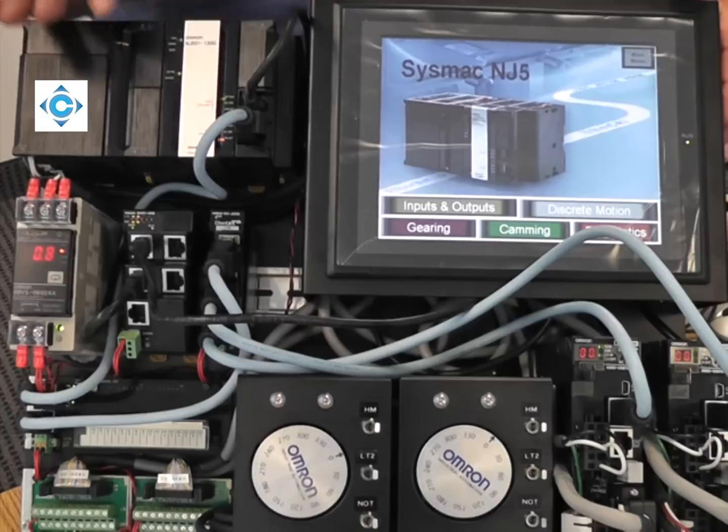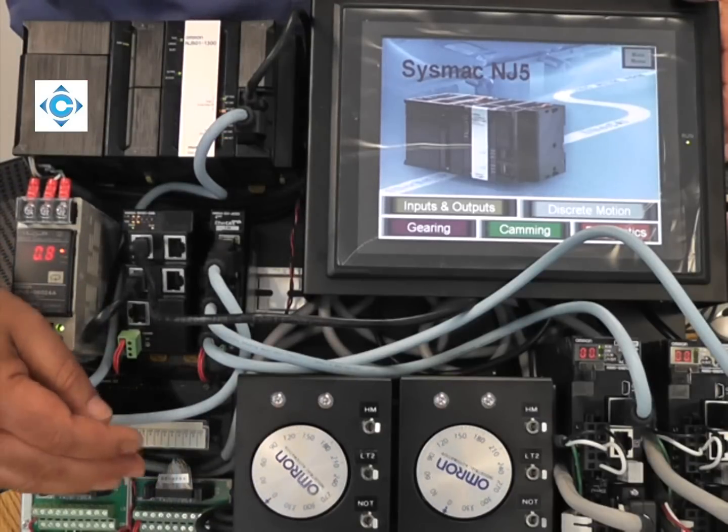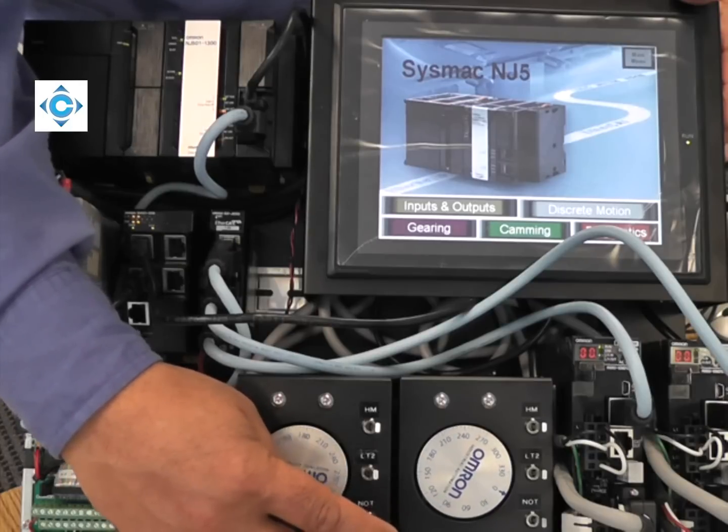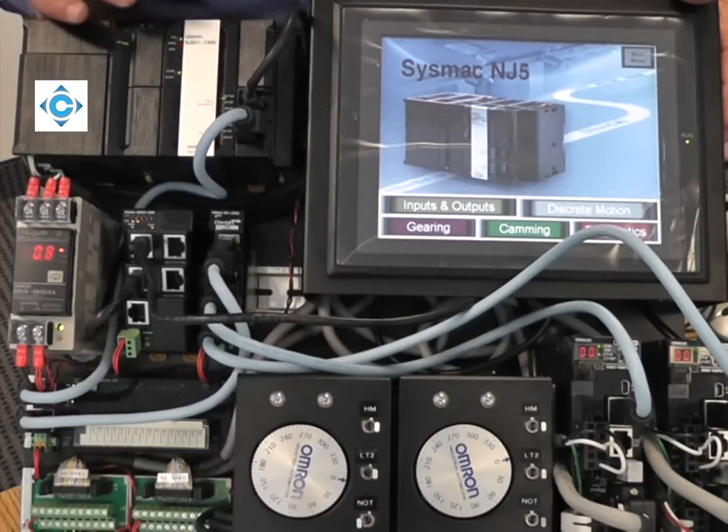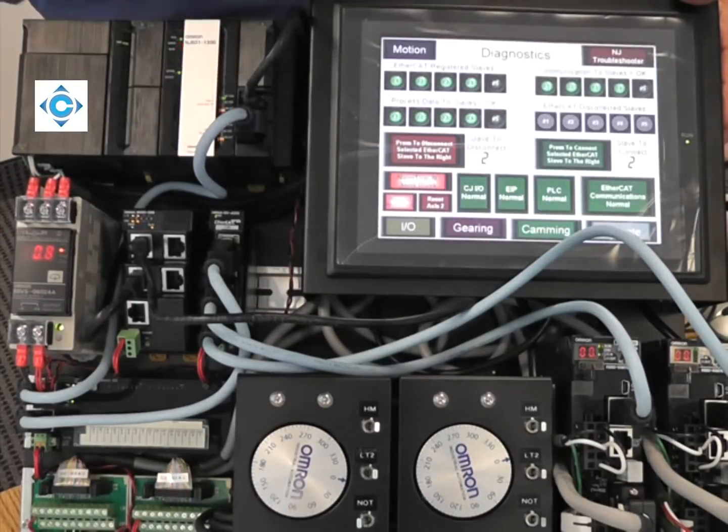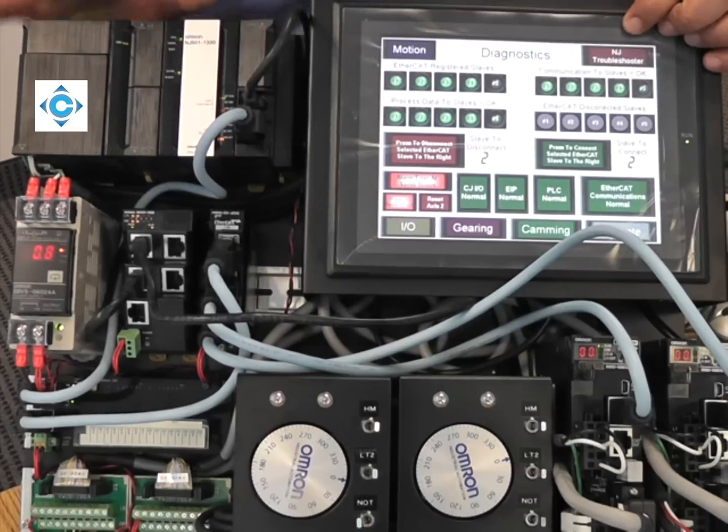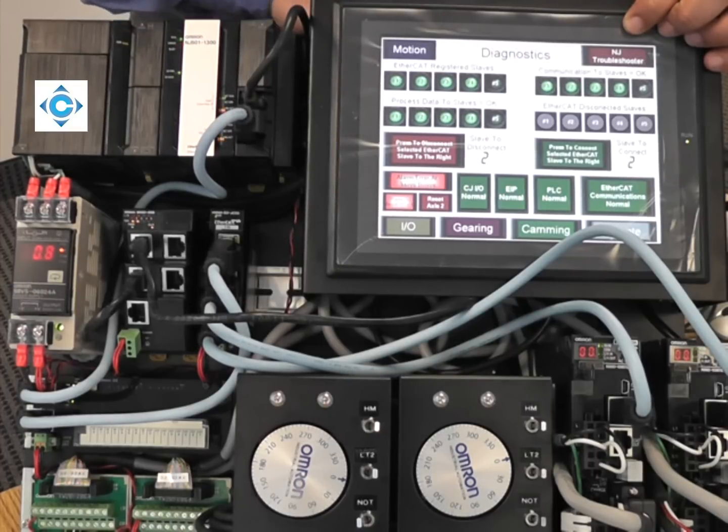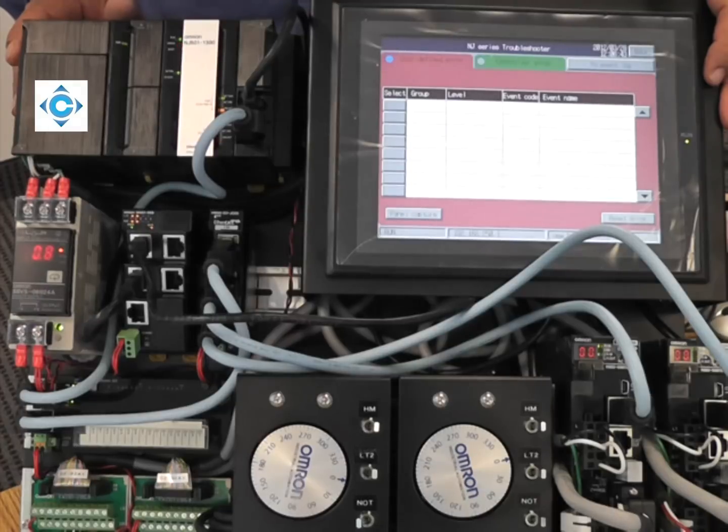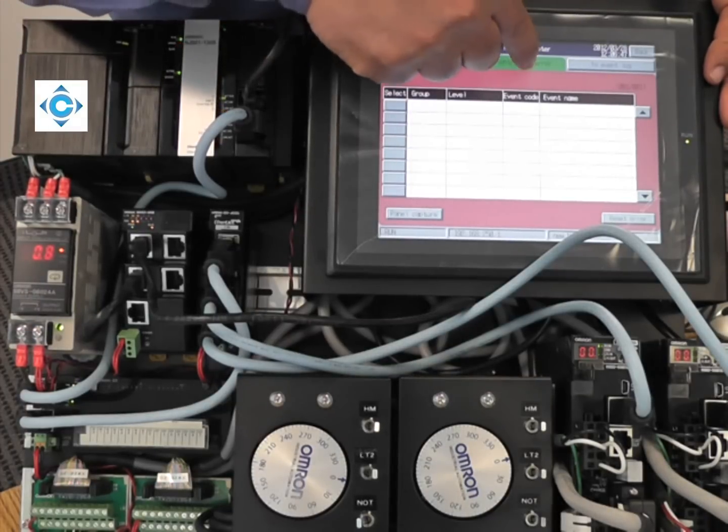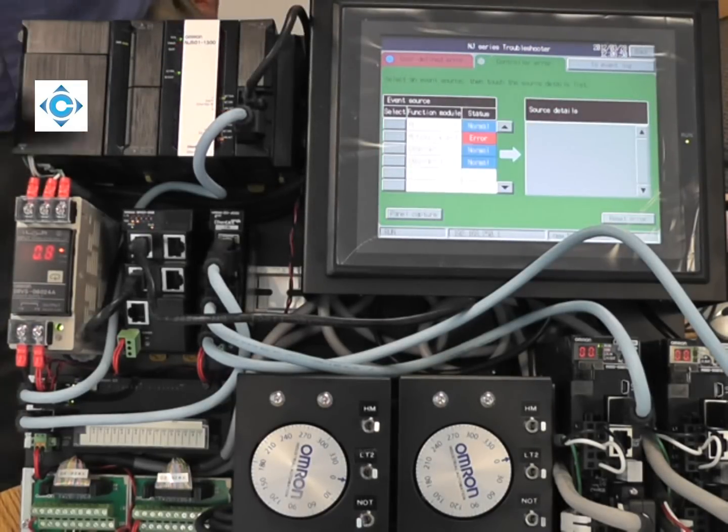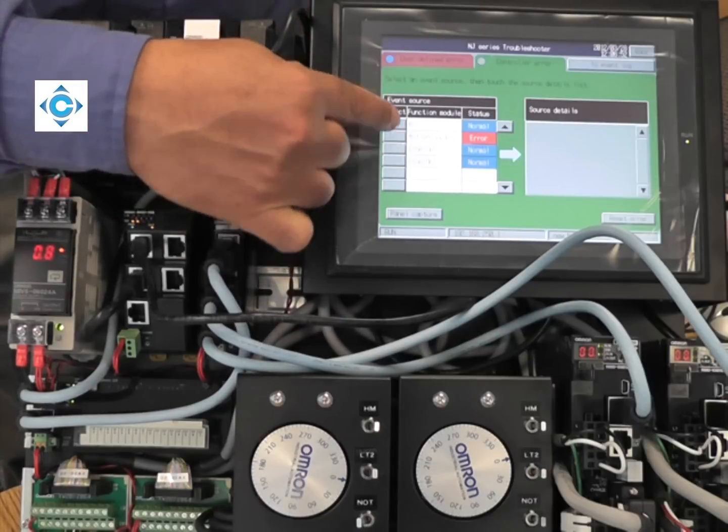Any fault will be categorized in one of these four. For example, while I am running my cam, I can generate a fault on the drive, the negative over-travel. Then I can go to diagnostics. This NJ troubleshooter is really built in the NS, nobody programmed it. You just have to activate it. When I go to this NJ troubleshooter, it should collect the faults. As you see here, this is the four processes: PLC, motion, EtherCAT, Ethernet IP.